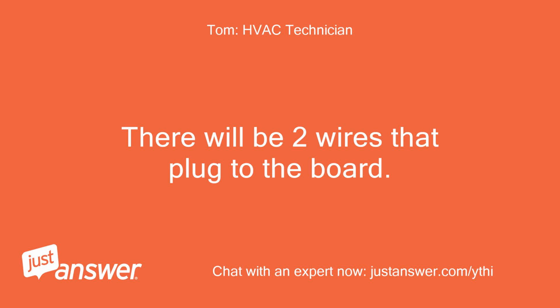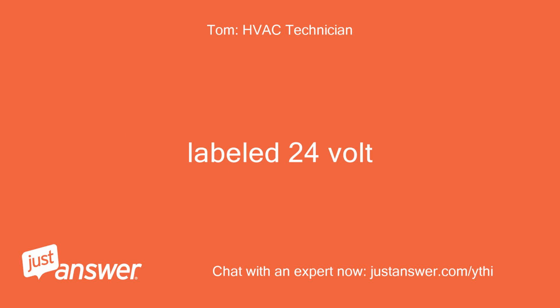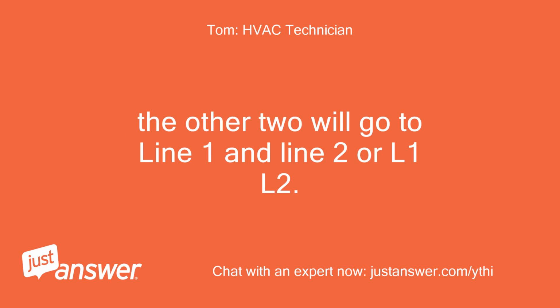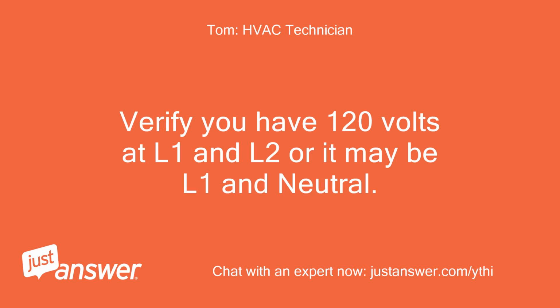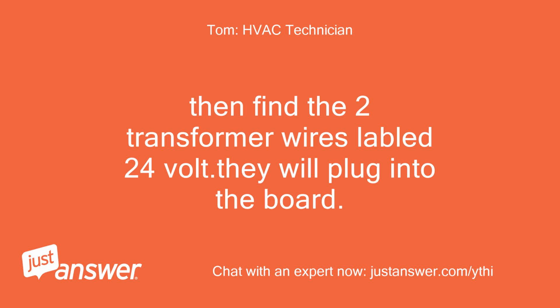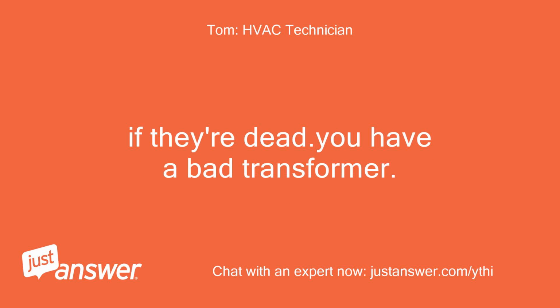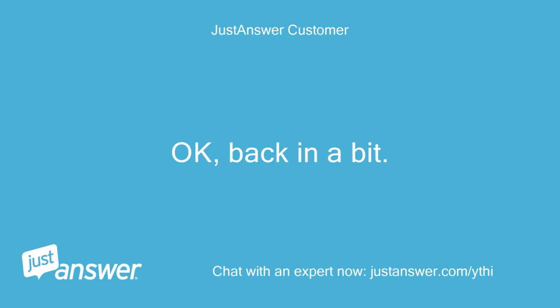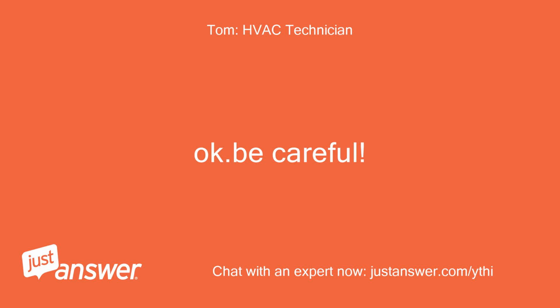There will be 2 wires that plug to the board. Labeled 24 volt. The other 2 will go to line 1 and line 2 or L1 L2. Verify you have 120 volts at L1 and L2, or it may be L1 and neutral. Then find the 2 transformer wires labeled 24 volt. They will plug into the board. If they're dead, you have a bad transformer. Okay, back in a bit. Okay. Be careful.